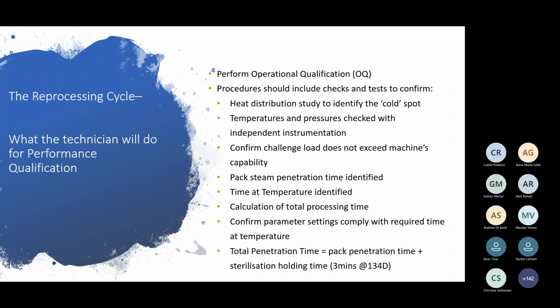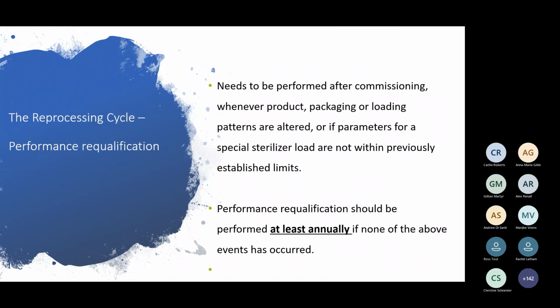They calculate the total processing time. So, if it takes an extra 30 seconds to reach the right temperature in your pack, then they will set it so that your time at temperature is set for 3.5 minutes to make sure that everything still has the right processing time. Confirm parameters, settings comply with required time at temperature, which I was just talking about. So your total penetration time equals your pack penetration time plus your sterilization holding time. So if that's 3 minutes at 134 degrees. I hope that was clear.